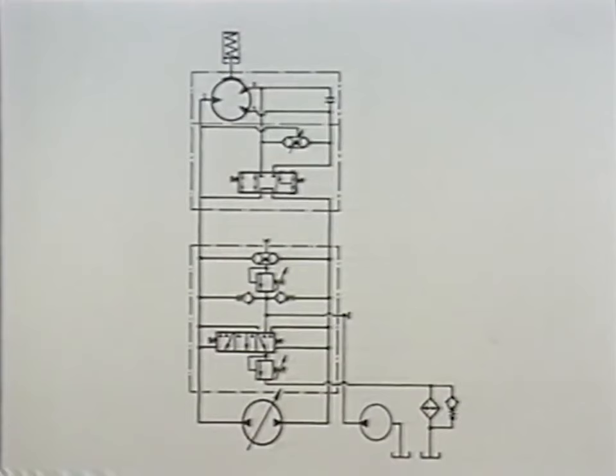Motor valve function at high speed. The hydraulic motor may be operated at half its normal displacement by introducing a so-called two-speed plug to separate the A and B connections of the hydraulic motor.